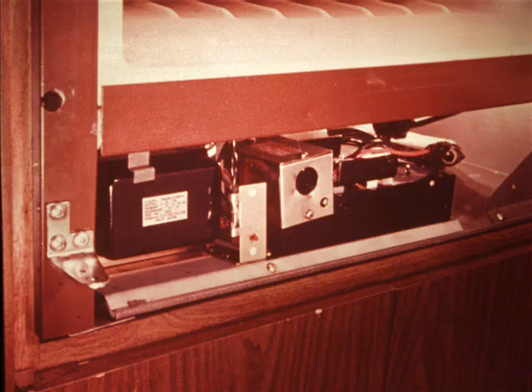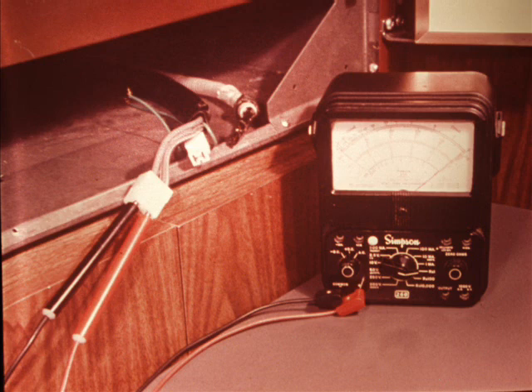In case of an inverter assembly problem, the inverter and the transformer are now replaceable individually. You do not have to replace the entire assembly. Here's how to test which part is at fault with an ohmmeter or a self-powered test light. First, disconnect both the 120-volt and 12-volt power connectors and the connector to the thermostat and compressor motor. And check the gray thermostat leads for continuity to be sure the problem isn't just the thermostat or its wiring.